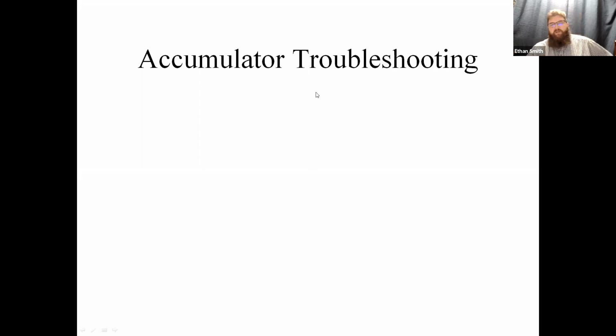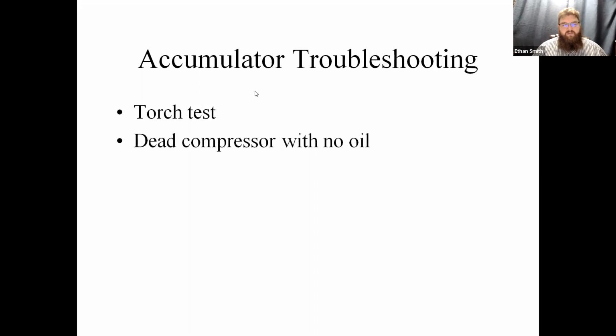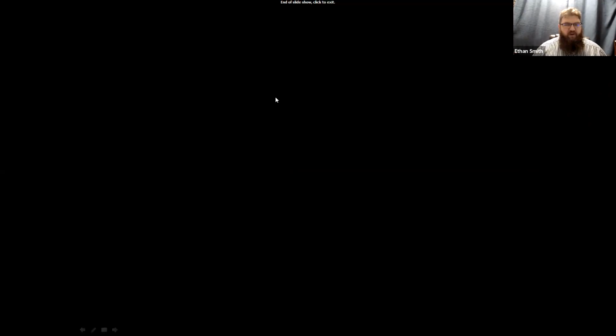Okay, let's talk about accumulators real quick. So you may be thinking, what's to diagnose with an accumulator? It's just a steel can with some pipes in it. You're absolutely right. But there is a situation where we can have a problem with accumulators. This usually needs to be done if you have a compressor failure. So I will always recommend, if you guys have a compressor failure in a heat pump and you've got an accumulator in there, let's troubleshoot the accumulator. So there's something called a torch test. We're going to do this, like I said, with a dead compressor with no oil.